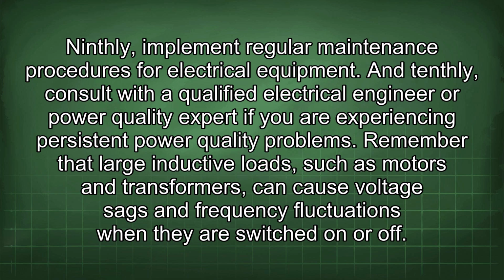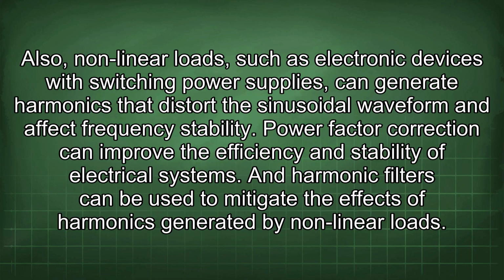Remember that large inductive loads, such as motors and transformers, can cause voltage sags and frequency fluctuations when they are switched on or off. Also, nonlinear loads, such as electronic devices with switching power supplies, can generate harmonics that distort the sinusoidal waveform and affect frequency stability. Power factor correction can improve the efficiency and stability of electrical systems, and harmonic filters can be used to mitigate the effects of harmonics generated by nonlinear loads.